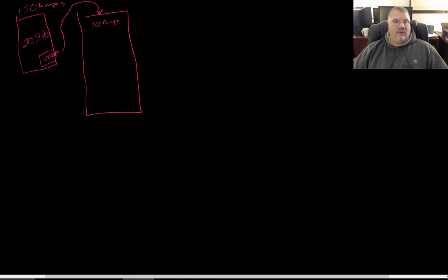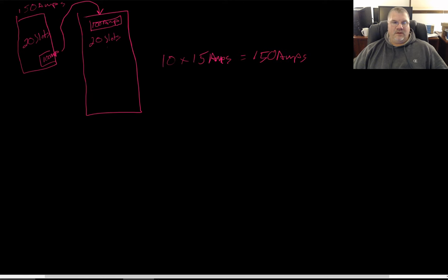Now I want to add a sub panel. From the main 150-amp panel I had two free slots, so I put in a 100-amp breaker there and ran wire to the sub panel, which also has a 100-amp breaker — that way I can switch in both places. The sub panel also has 20 slots. If I fill it with ten 15-amp breakers that's 150 amps on paper, but again, not everything will be on at the same time.